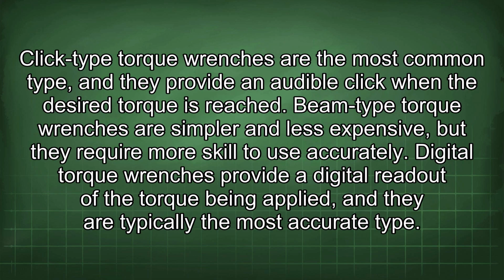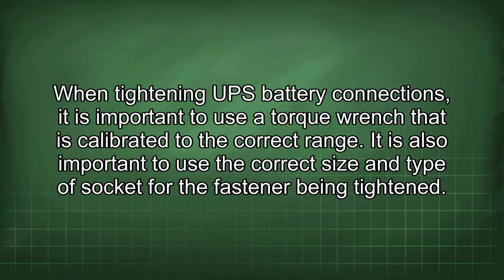Click type torque wrenches are the most common type, and they provide an audible click when the desired torque is reached. Beam-type torque wrenches are simpler and less expensive, but they require more skill to use accurately. Digital torque wrenches provide a digital readout of the torque being applied, and they are typically the most accurate type. When tightening UPS battery connections, it is important to use a torque wrench that is calibrated to the correct range. It is also important to use the correct size and type of socket for the fastener being tightened.